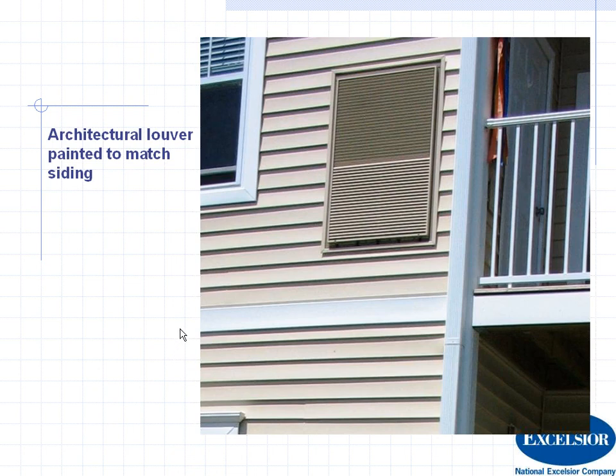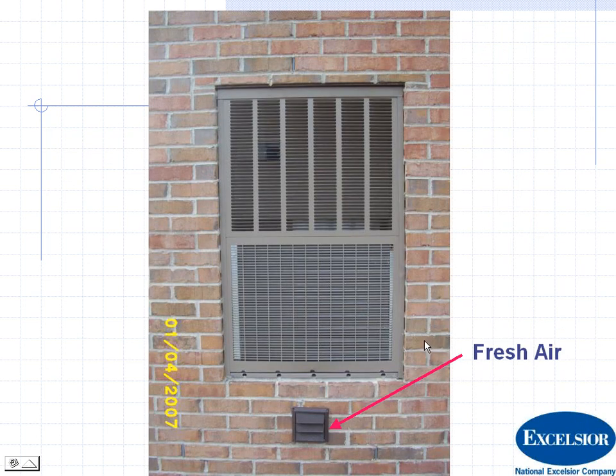This is a picture of what the grill looks like, and this is an architectural grill. It looks like this grill is just covering the unit itself, but if you want to get an architectural grill that covers the sleeve, that would come over here, so it would just be a much nicer finish to that. But that choice is up to you. I've seen these units with fresh air, just a little fresh air louver underneath that's mixed with the return air. So you can have that option in case you have some code requirements that you're trying to meet. Also in this picture you can see where the weep holes are, so you can see where some of the condensate does come out.